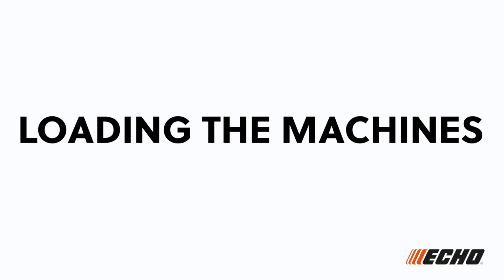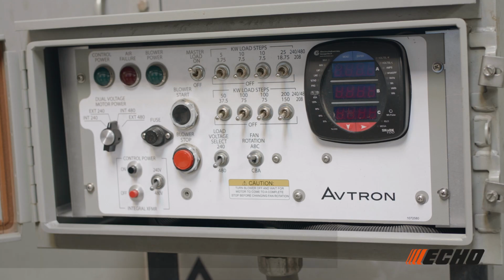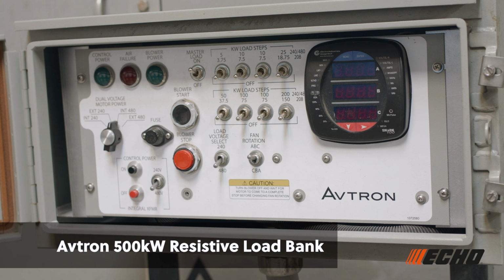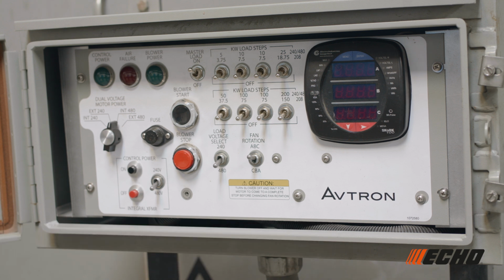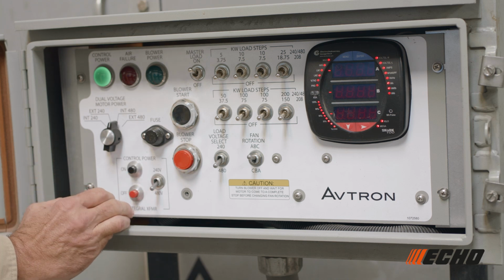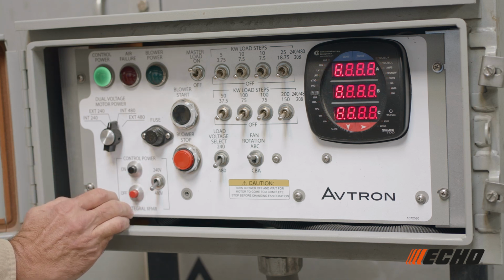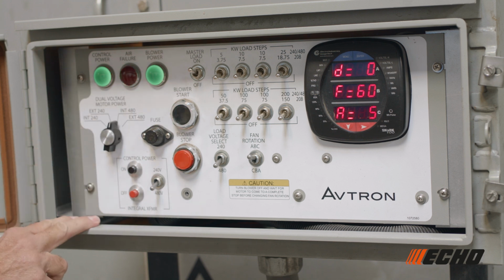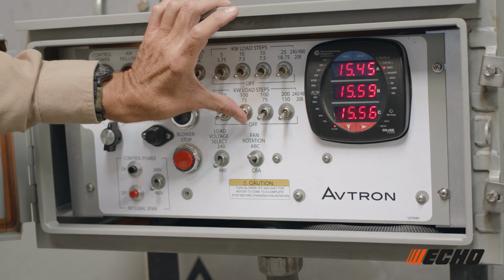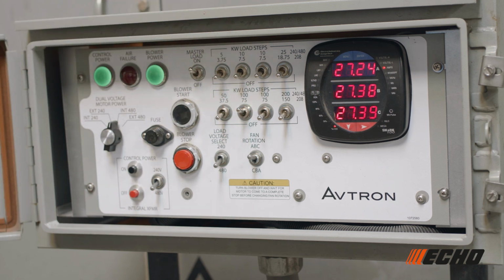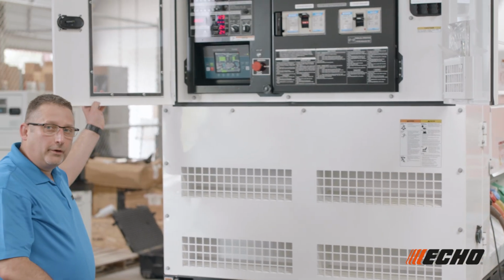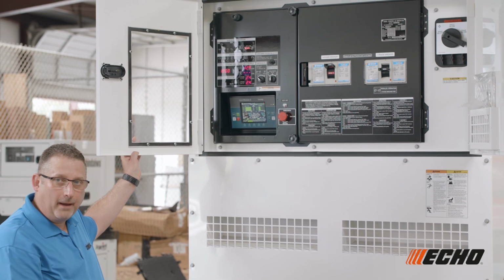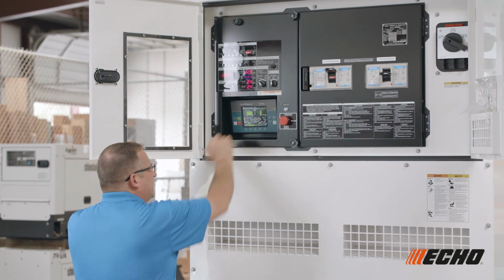We're going to go ahead and load the machines. For this portion, we're going to use a Avtron 500 kW load bank, and we're going to apply 100 kW of load to start with. Let's go ahead and start it up. Turn the fan on. You'll notice that we have 129 kVA of remaining load available. We're running at about 65 amps per leg.